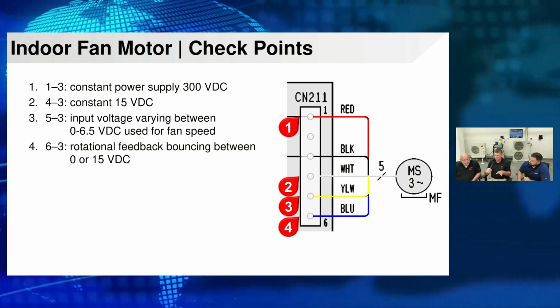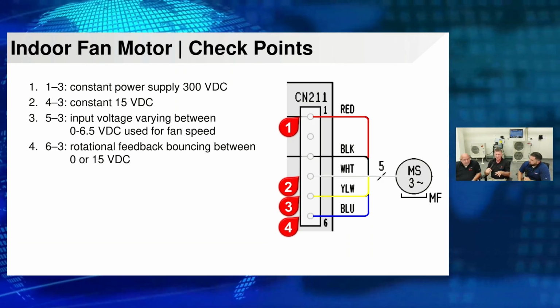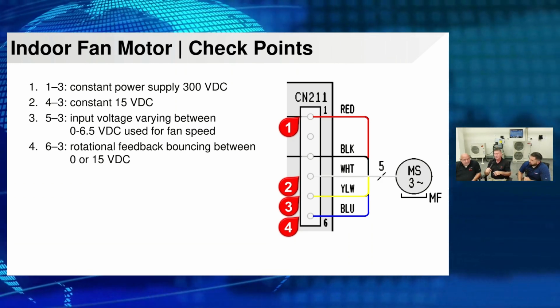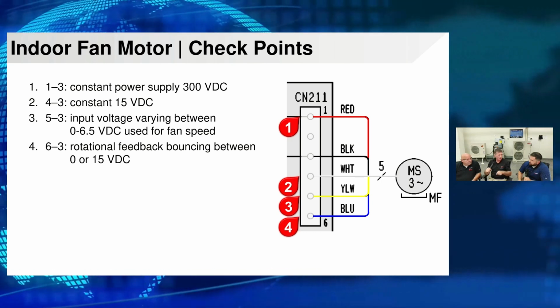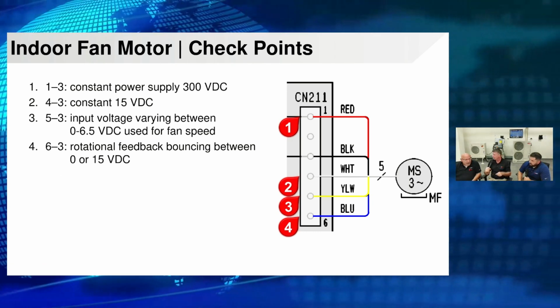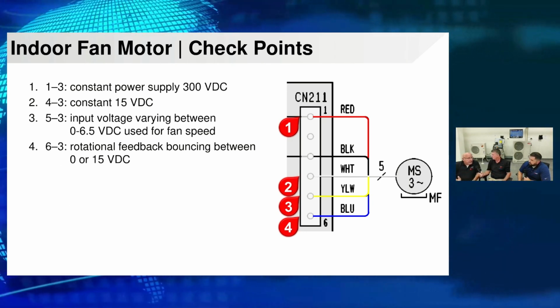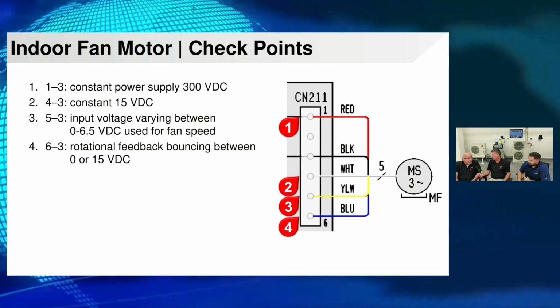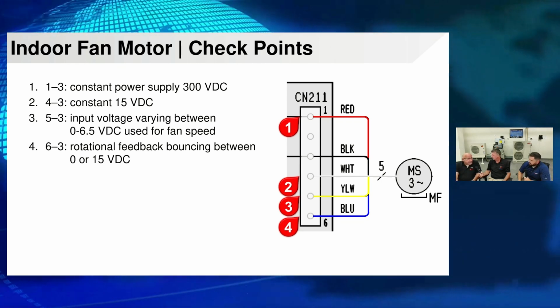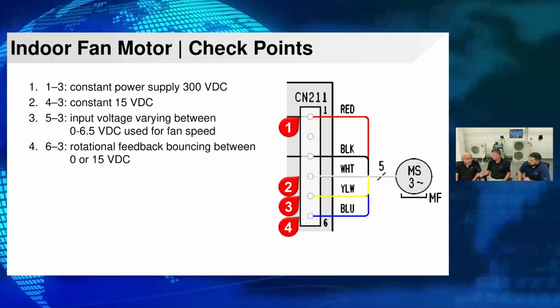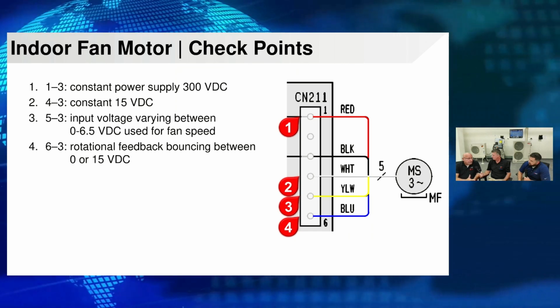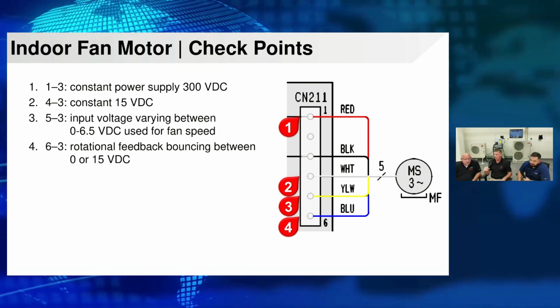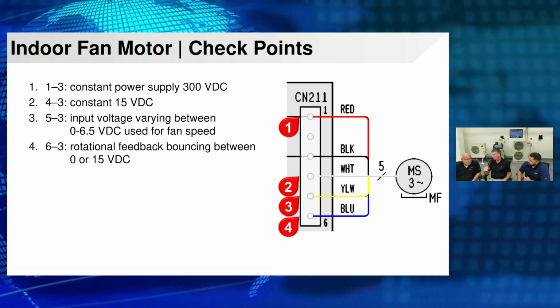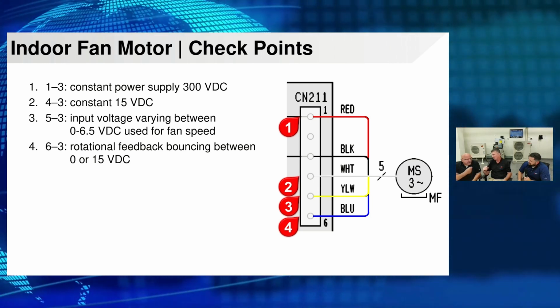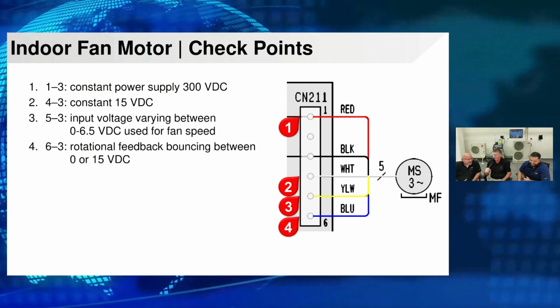Correct. So if we're actually working on a live system and we're going to disconnect that plug, we want to make sure not only to kill power, but give it a minute, let that thing bleed down. And the way to do it is to wait for the lights to go out. And to confirm it, you can find a DC bus. As long as you're at 30 volts DC or below, you're good to go, discharged. Should be safe. Even 9 volts won't kill you. Put it on your tongue, it'll... 9 volts, all right. 30 volts, yeah.